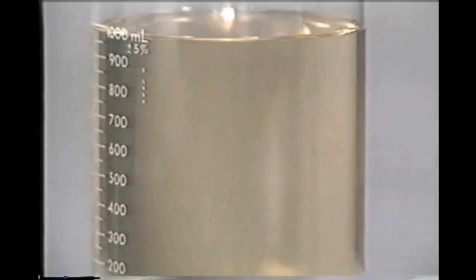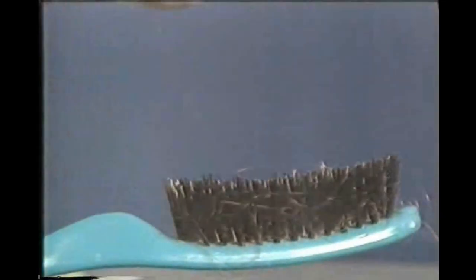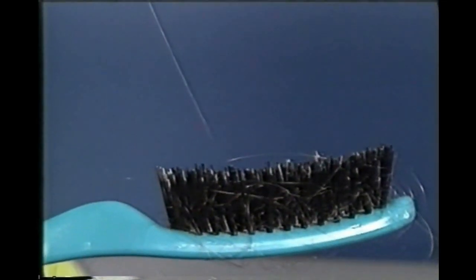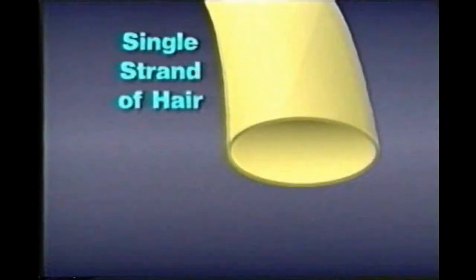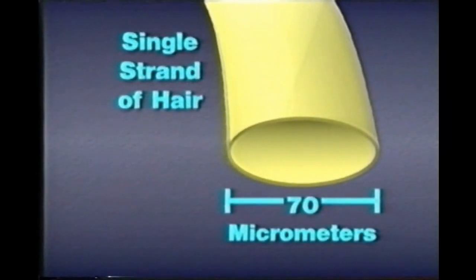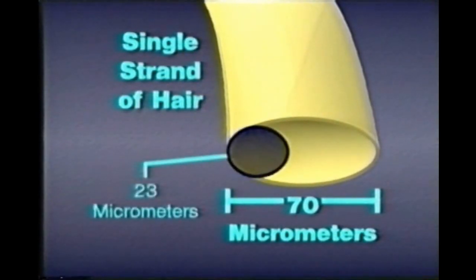Hydraulic fluid clean enough for modern hydraulic systems must have no particles larger than about one-third the diameter of a human hair. The end of this shaft of hair, which is about 70 microns, or 70 millionths of a meter across, is three times as large as the acceptable size for particles in hydraulic fluid. In some systems, even that would be too big.